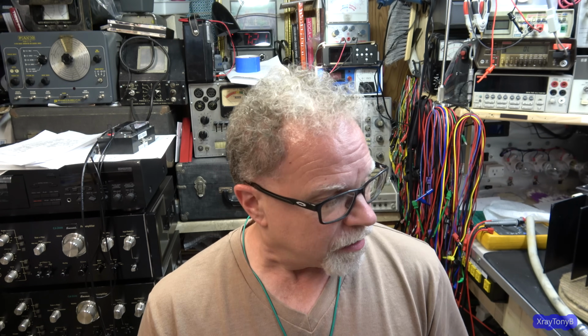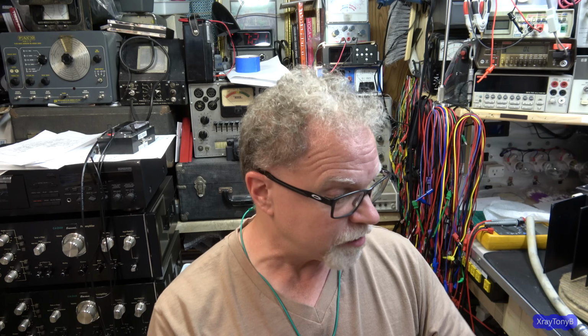What does that mean? Well, the maximum breaking voltage of a fuse is the maximum voltage where, when the fuse opens, it will open the circuit in the allotted time specified in its spec sheet. So that means you can't just put a fixed time on how long it takes a fuse to blow, because it really depends on a bunch of things.